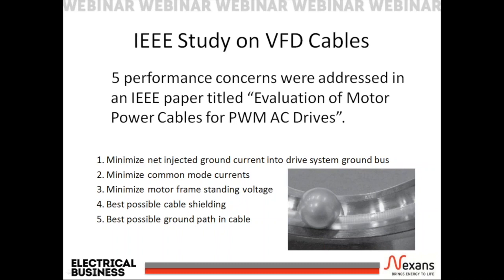Number 1, minimize net injected ground current into drive system ground bus. This improves the drive system performance and increases the reliability of drive electronics. Number 2, minimize common mode currents. This reduces the possibility of bearing currents, which cause the bearings to become pitted and fail from what seems like a mechanical mode of failure.